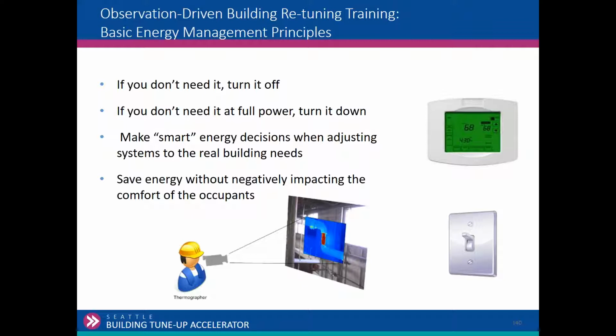And one thing is, you can implement a measure, but sometimes measures affect other measures. You reset this, you go, I'm going to save a bunch of energy and set up a reset schedule for my discharge air, and now all of a sudden you've got a room that's overheating because the air's not cold enough. So we do want to think about, are there areas that are dry? Am I going to create a problem? Has anybody created a problem by doing a temperature reset? Right. Never. Right. That's the only way you learn. I slowed the fan down too much. I slowed the pump down too much, or whatever that is. Or now my chiller is not behaving correctly because I don't have enough flow or I don't have enough load on it. So we just want to think about that.